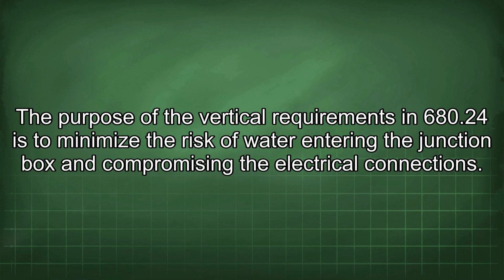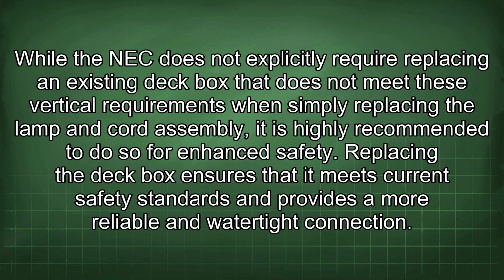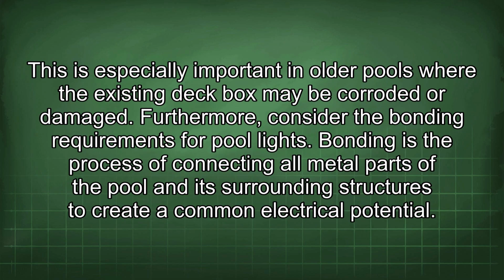The purpose of the vertical requirements in 680.24 is to minimize the risk of water entering the junction box and compromising the electrical connections. While the NEC does not explicitly require replacing an existing deck box that does not meet these vertical requirements when simply replacing the lamp and cord assembly, it is highly recommended to do so for enhanced safety. Replacing the deck box ensures that it meets current safety standards and provides a more reliable and watertight connection. This is especially important in older pools where the existing deck box may be corroded or damaged.